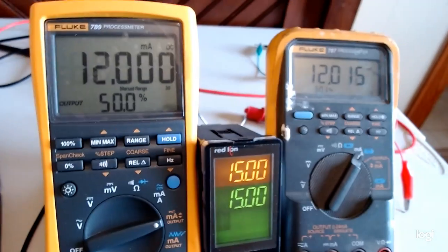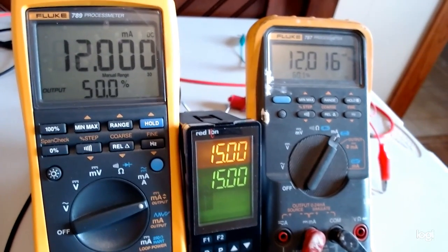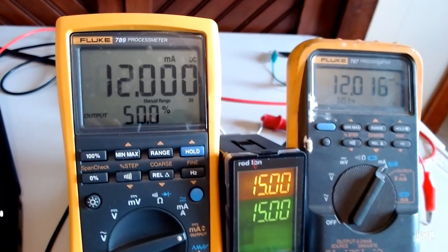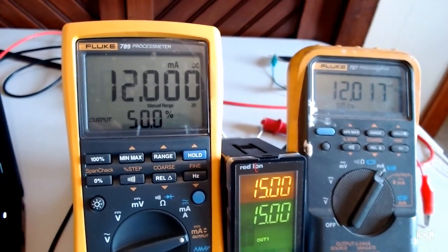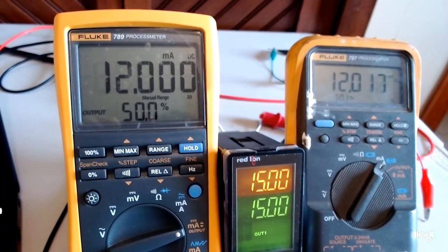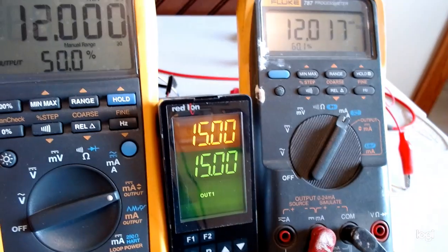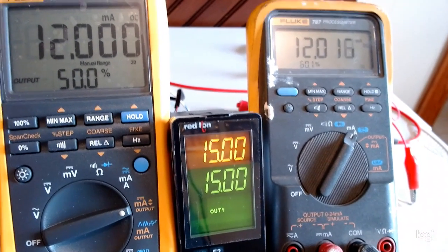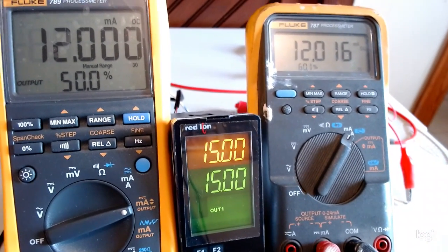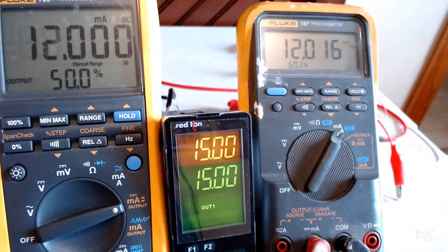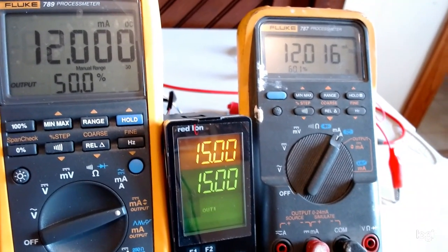All right, we are back, and again, we've still got a gain of 1. Our process variable on the left meter, that's our measurement from our level transmitter coming in. It's saying that we've got 50%, a 12 milliamp signal, which means we've got 15 inches of water in that tank. That tank's calibration range is from 6 to 24 inches of water, and 15 inches of water in there is going to be 50% of the level, okay?